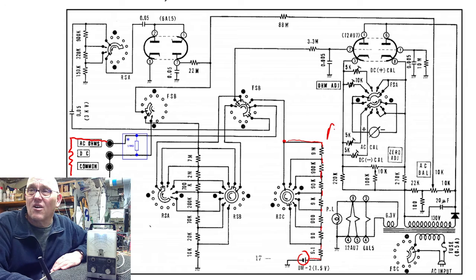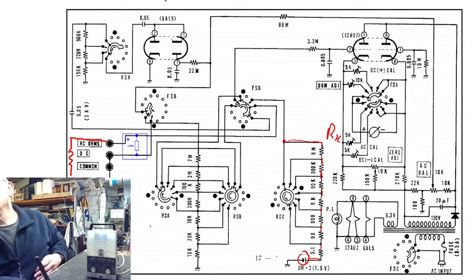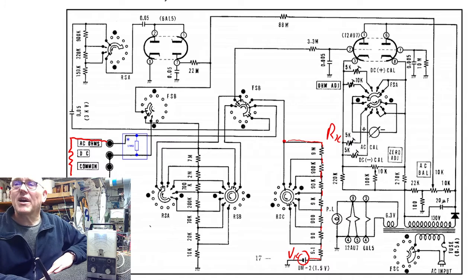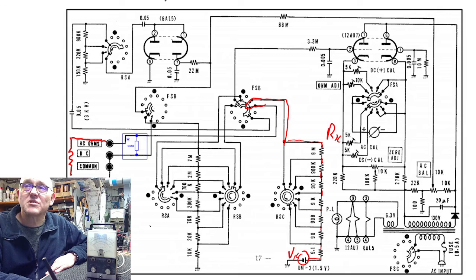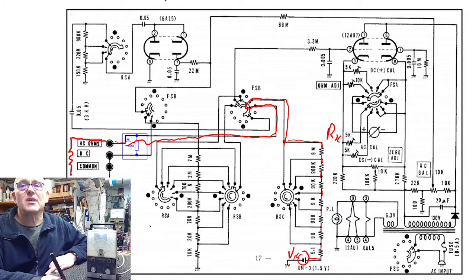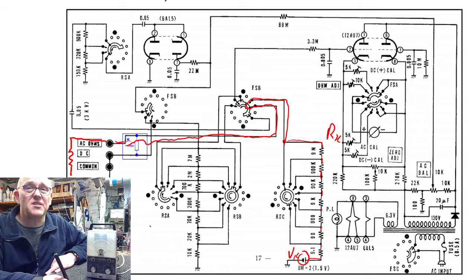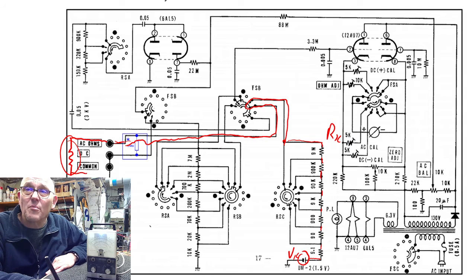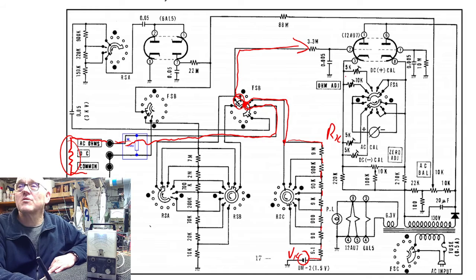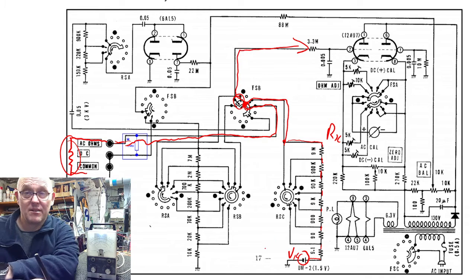So there's my RK, my known resistance, and my voltage that's known, VK, and now my current passes through the function selector switch and out through the AC ohms and through the terminal and through my resistor under test to ground, and I have a completed circuit. And now this section over here, you can see it's common at the switch, and this tab over here will short out the whole system so that I can take a measurement of the voltage at this point over here, bring it to the input of my meter driver and get a representative voltage.